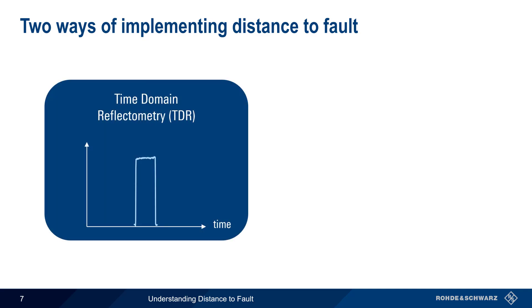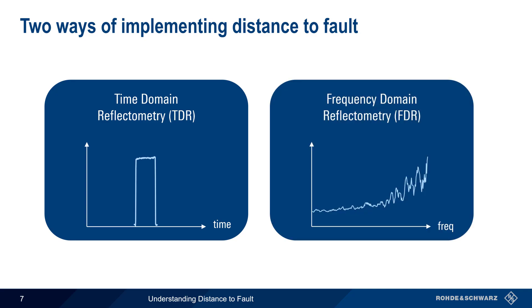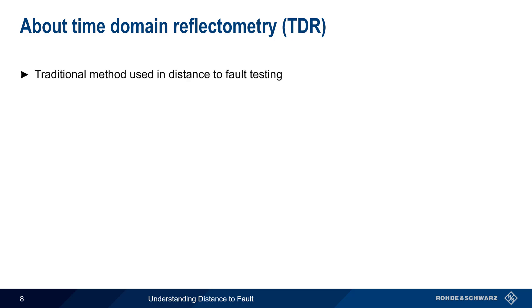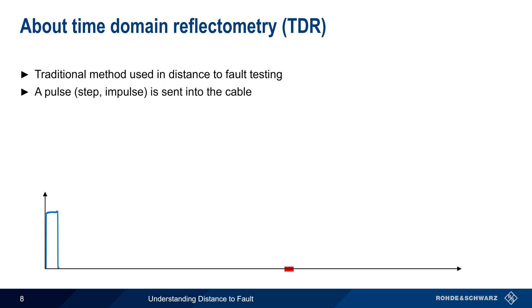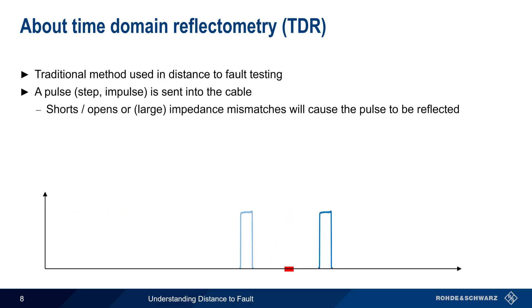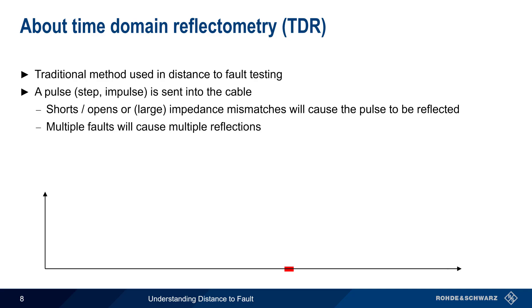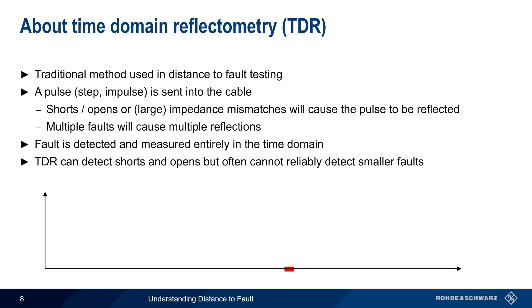Distance to fault can be implemented using time domain reflectometry, or TDR, and using frequency domain reflectometry, or FDR. In TDR, a pulse or other short duration signal is transmitted into the cable. When this pulse encounters a short, an open, or a large impedance mismatch, some portion of this pulse's energy will be reflected. If multiple faults are present, this will cause multiple reflections. Faults are detected and measured entirely in the time domain, by observing the time delay between when the pulse was transmitted and when reflections are received. One drawback of TDR is that it can generally detect shorts and opens, but often cannot reliably detect smaller faults.